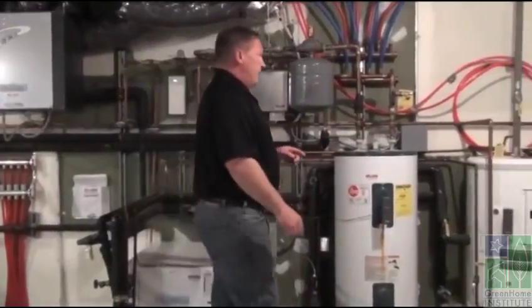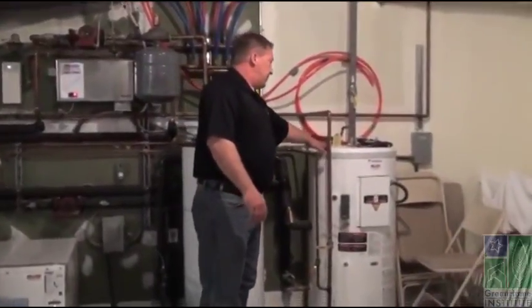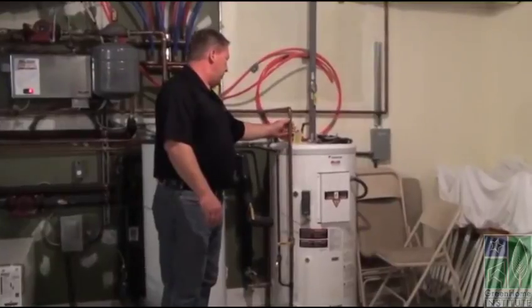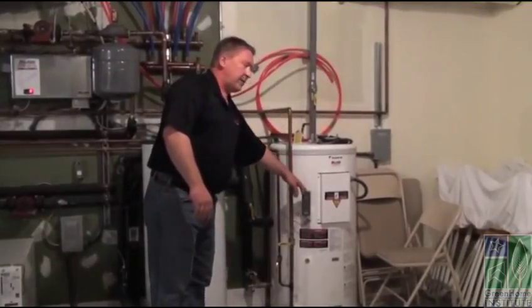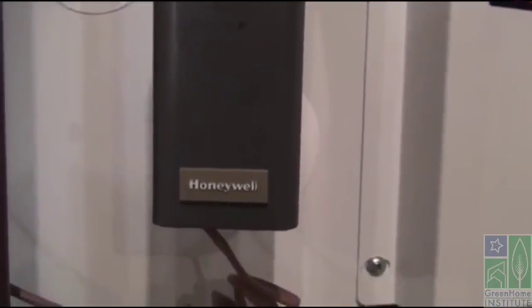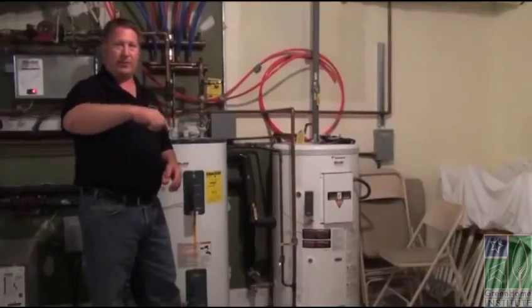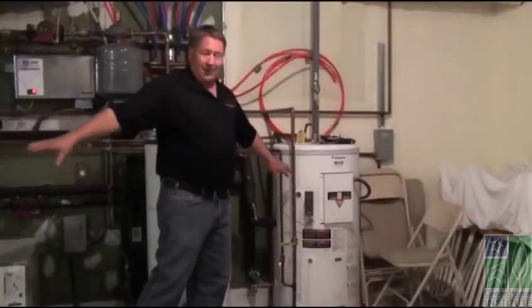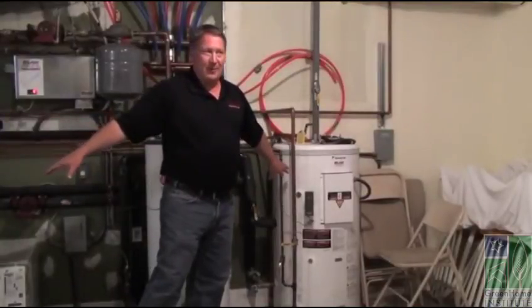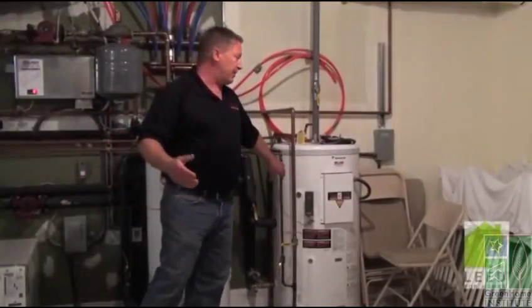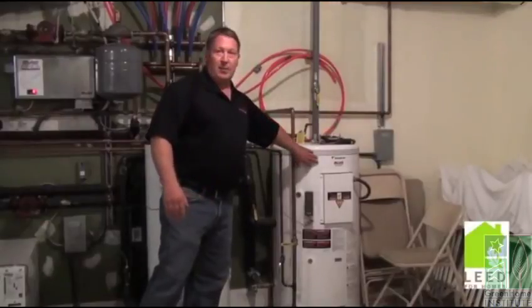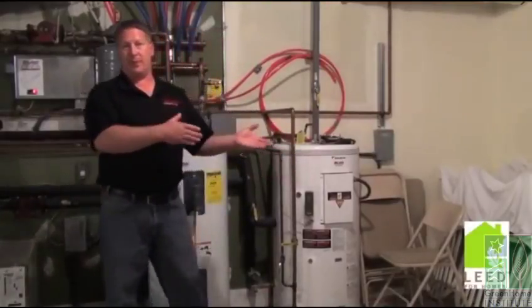There's one other system here that's the hot water heater, and the geothermal system has a zone that will heat your hot water. There's a thermostat here that controls that temperature. So this system actually has a coil going around the outside of the tank that will deliver hot water from the geothermal system at about 110, 120 degrees, and that transfers into the hot water so you can make hot water for your domestic use.